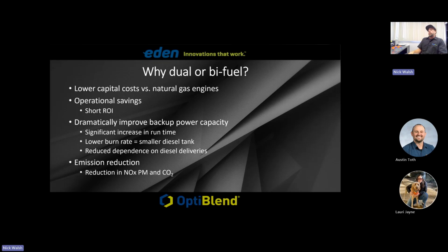So you can dramatically improve your backup power capacity. If we're cutting the diesel in half, your on-site storage tank will either last twice as long, or you can have a smaller on-site storage tank. Some areas of the country, the EPA says you can only have X amount of gallons on site or underground.